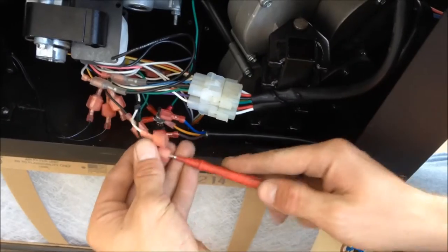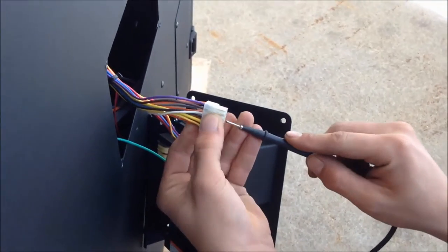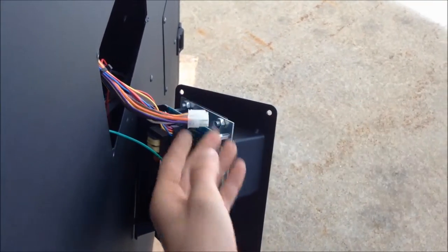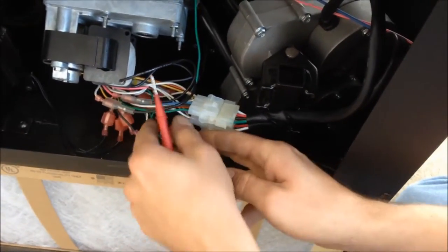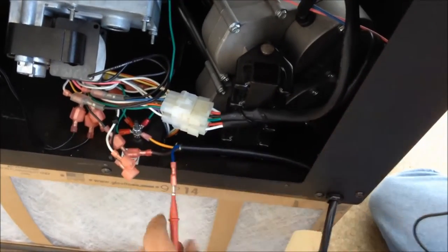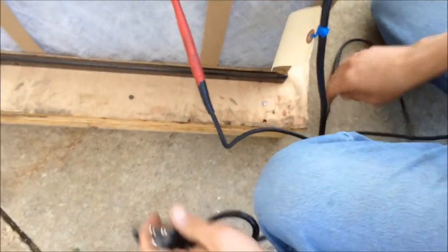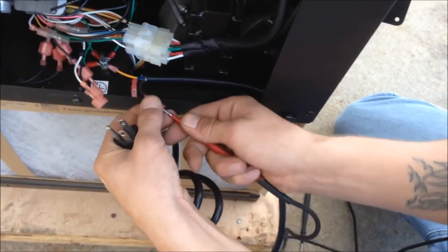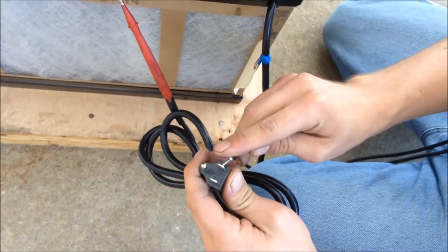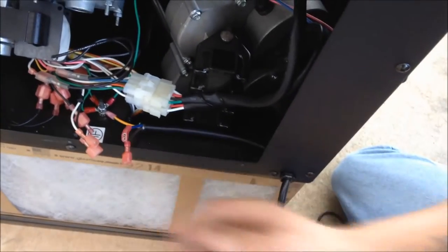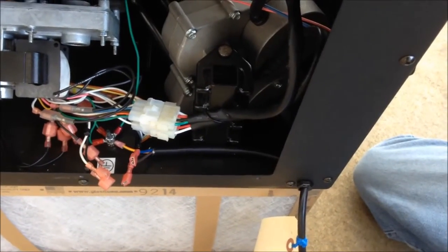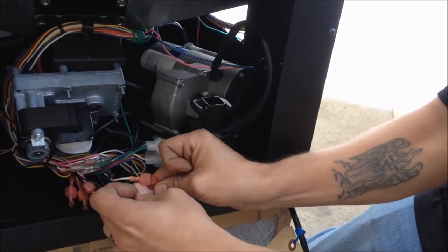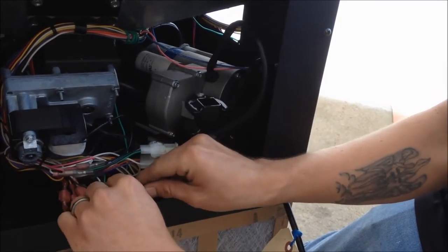Now we're going to check the black to the black. No break in the line. I'm going to check for any punctures in the power cord. We're going to check the power cord. No break in the line. So this indicates we have no breaks in the line, no punctured wires, melted wires, and we have good connection from the power cord to the control panel. So we're going to go ahead and plug those back in.